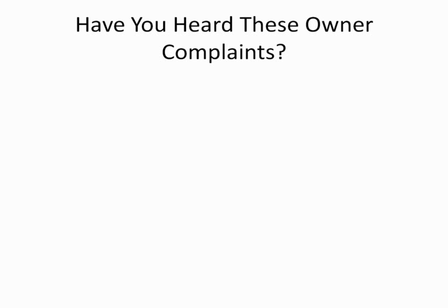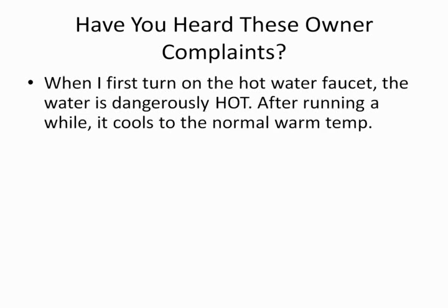So the one thing we start with is, have you heard these owner complaints? The first one, and I get calls on this all the time, is: when I first turn on the hot water faucet, the water is dangerously hot. I get scalded. And then after it's running a while, it cools down to its normal warm temperature, and we're okay. That's probably the most common complaint that I hear. What the heck is happening? The guy installed this correctly. Can you come out and take a look at this?